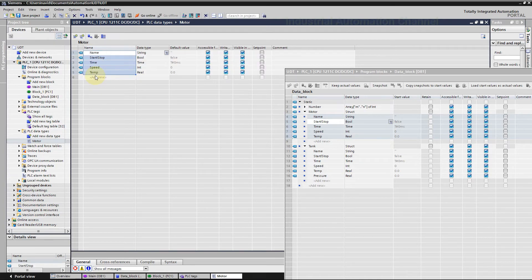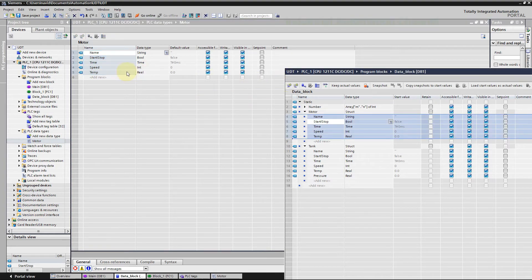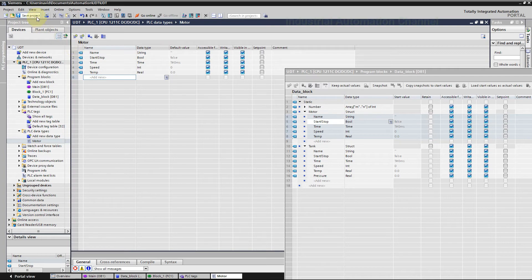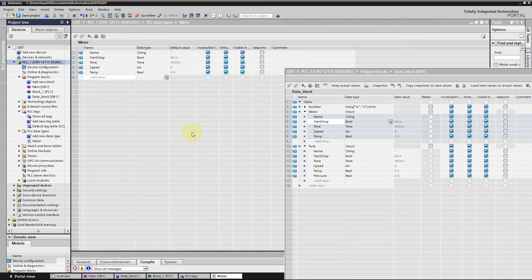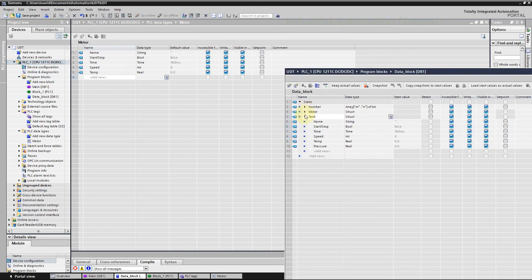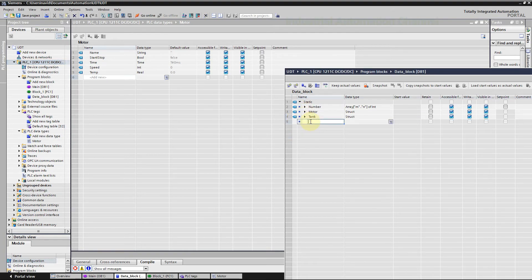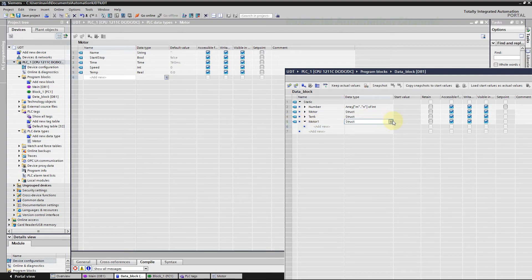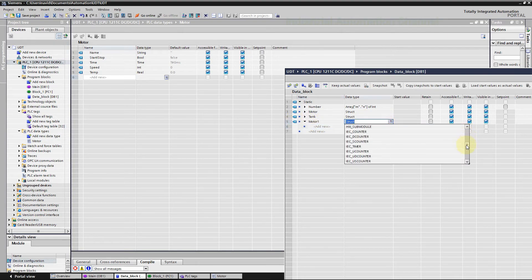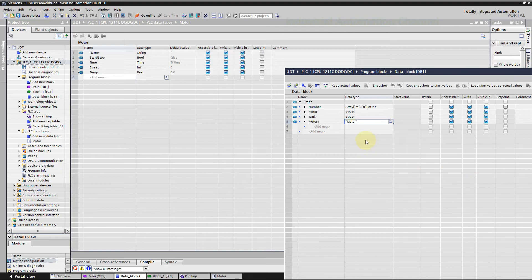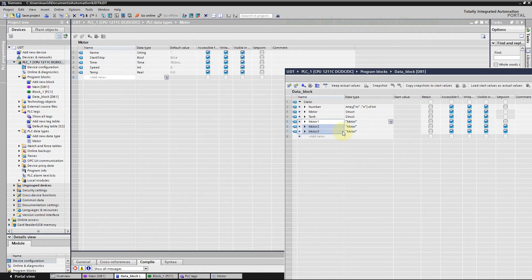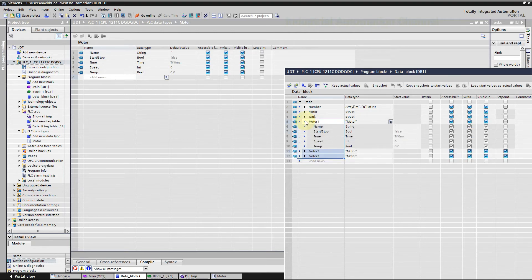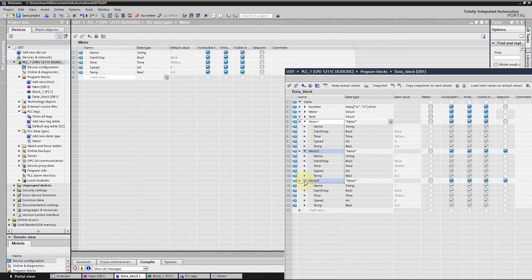Copy all the tags for the motor. Now like a struct we have defined a data type that consists of different data type tags. If you go to the data block we can define tags for different motors using our UDT. But before that, click on PLC and compile the program. If you don't do that, PLC will not have access to the UDT. Expand this menu to choose data type and scroll down to the bottom. We should see the UDT that we have just created before. Create another tag motor 2 and 3 and so on. If you expand each motor, you will see the same data type that we have defined inside the UDT.